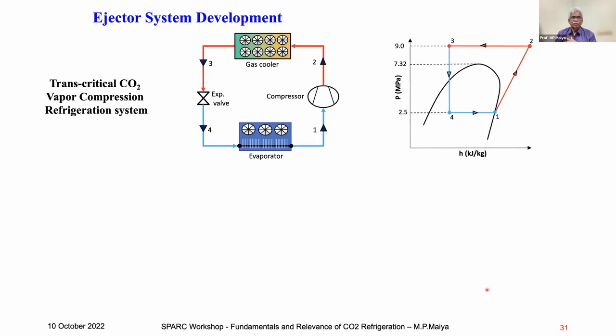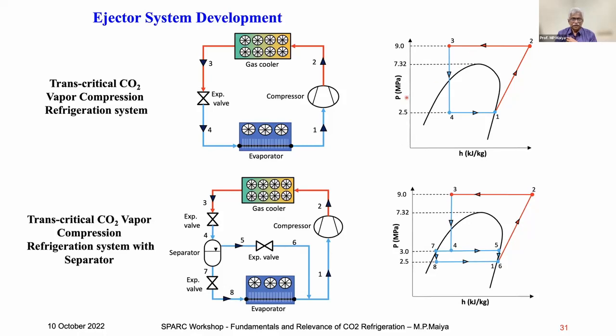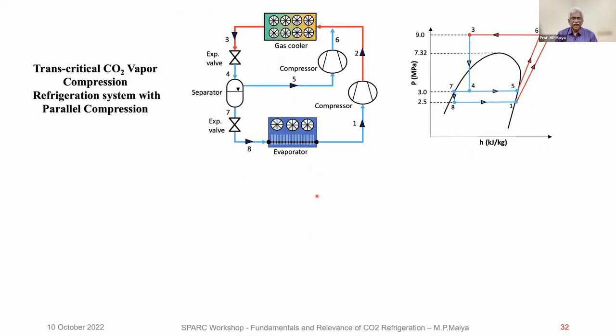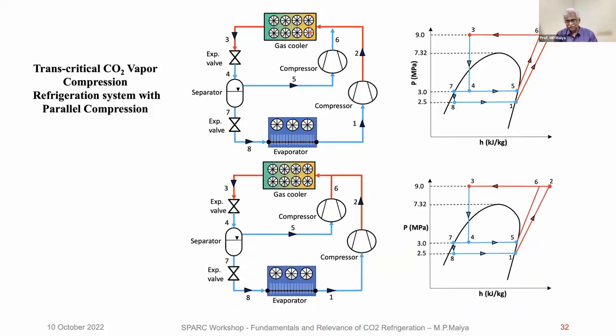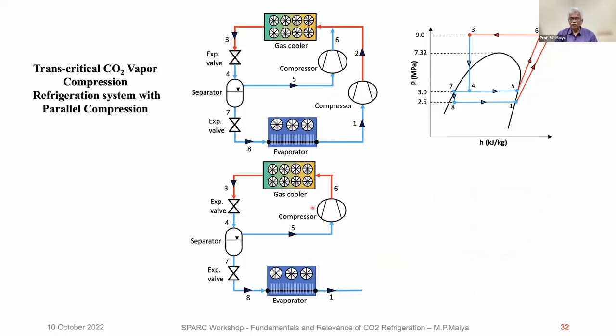This is the ejector system development. This is the transcritical system. This is one improvement to pressure you can make: throttle to intermediate pressure and separate the gas. Okay. Of course, thermodynamically both will be the same, no advantage thermodynamically. Now instead of that, you can send it to parallel compression. Instead of throttling and coming back, you can directly compress. So it's parallel compression, and it improves the efficiency. Now we will go for the ejector system instead of that. These both are the same now. Okay. Now I'll remove that.